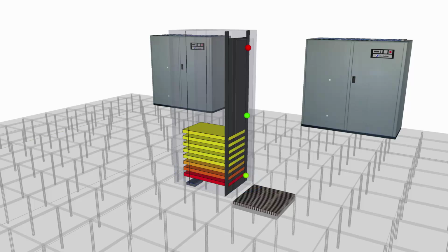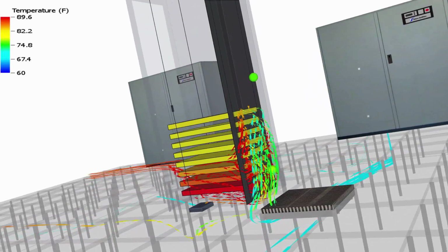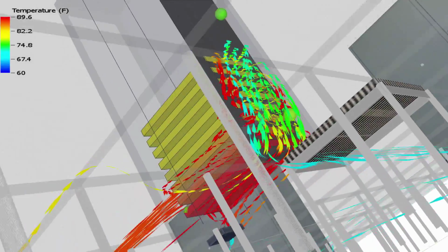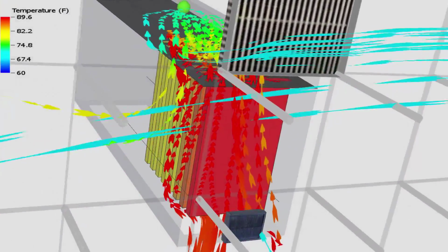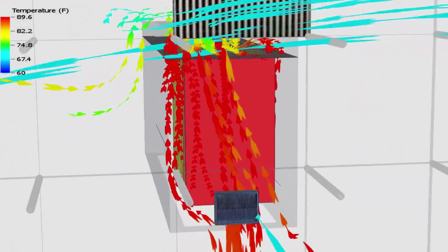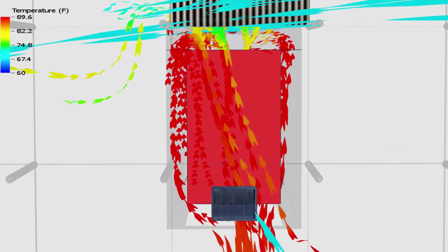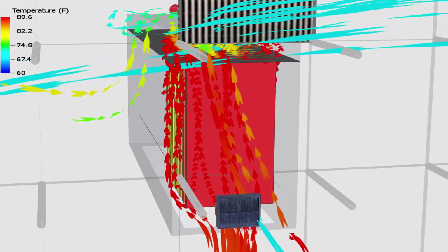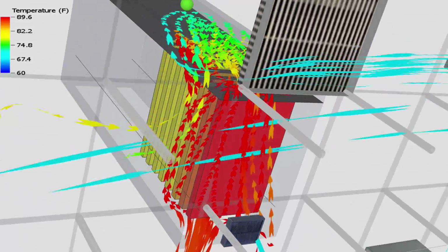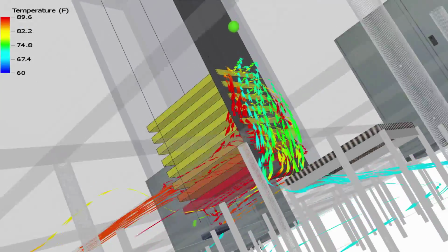That may not seem possible, but by animating the pathway of air delivered to the IT equipment using streamlines, we can see that there is recirculation under the cabinet that is causing the overheat. Even when completely blanked, leakages can still happen under and around the mounting rail.